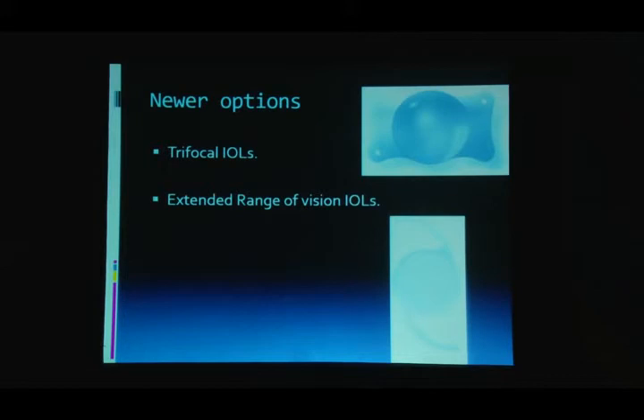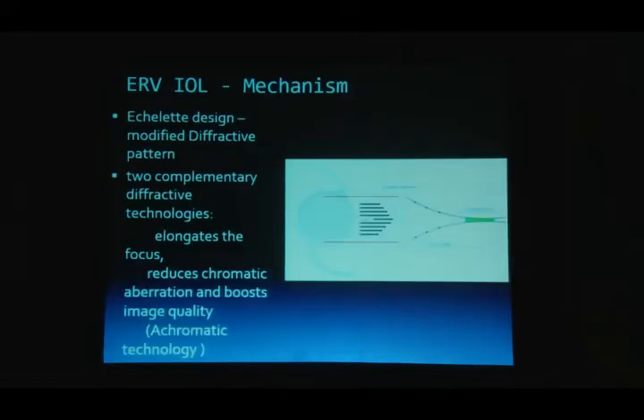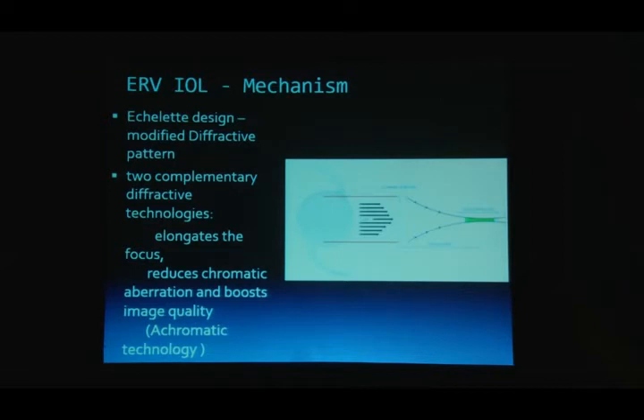Extended range of vision (EDOF) lenses work differently from diffractive designs. The Echelette design used here creates multiple foci so close to each other that the whole range becomes one continuous focus of vision. This EDOF technology uses two complementary mechanisms: it elongates the focus, and it minimises chromatic aberration. In chromatic aberration, blue light focuses in front of the retina and red behind, while green focuses on the retina, creating a blur circle on the retina and reducing image quality.